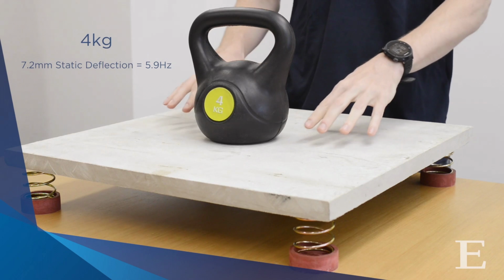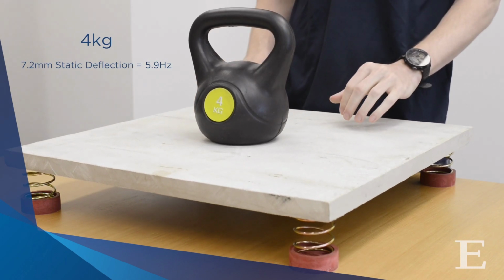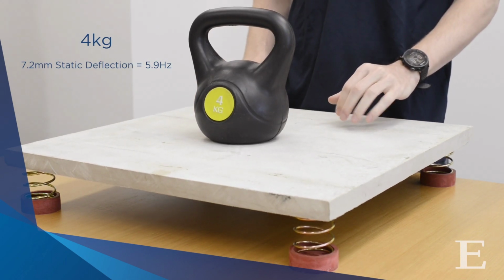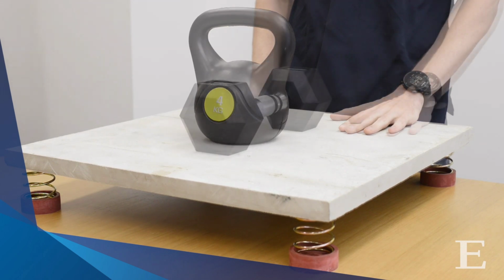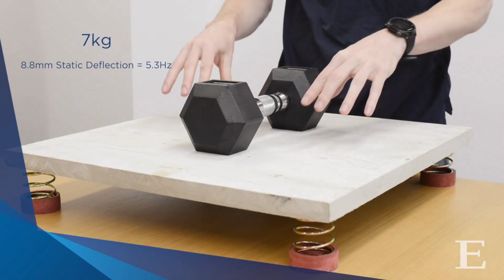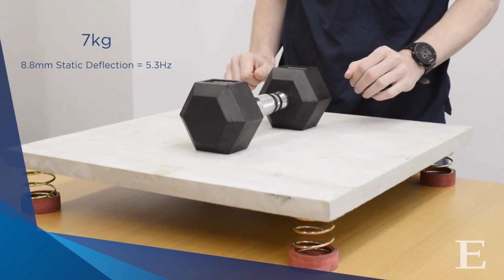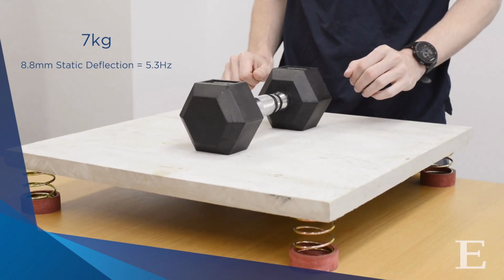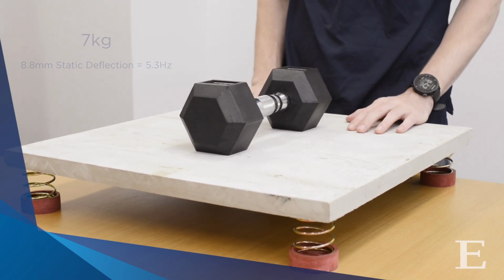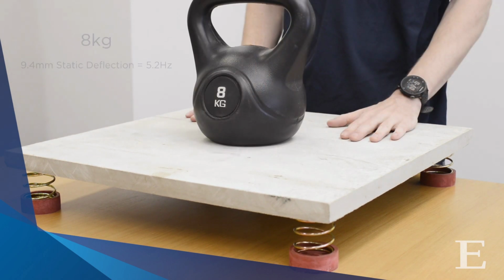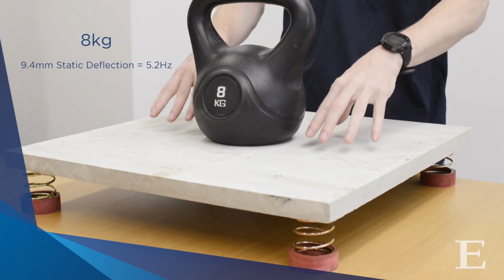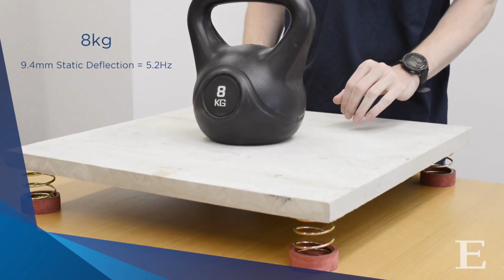So natural frequency is what we ultimately want to determine, and the static deflection represents a simple way of calculating this so that we can select appropriate springs. Should note, however, this only works with the assumption of linear stiffness isolators. For non-linear springs and most rubber mounts, static deflection isn't a really accurate way to determine the natural frequency and isolation performance.